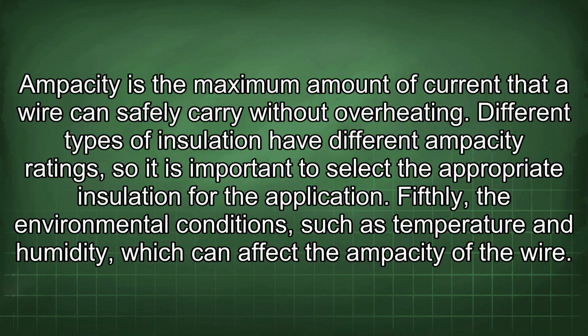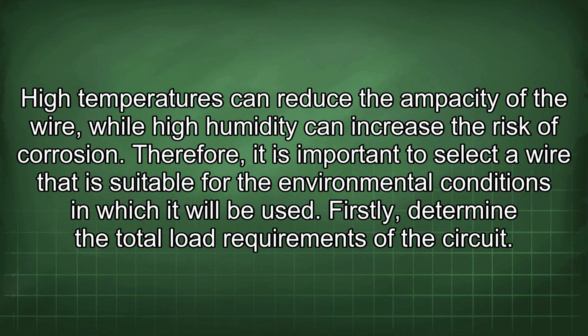Fifthly, the environmental conditions, such as temperature and humidity, which can affect the ampacity of the wire. High temperatures can reduce the ampacity of the wire, while high humidity can increase the risk of corrosion. Therefore, it is important to select a wire that is suitable for the environmental conditions in which it will be used. Firstly, determine the total load requirements of the circuit.